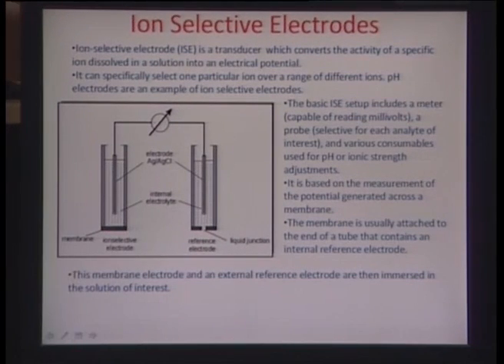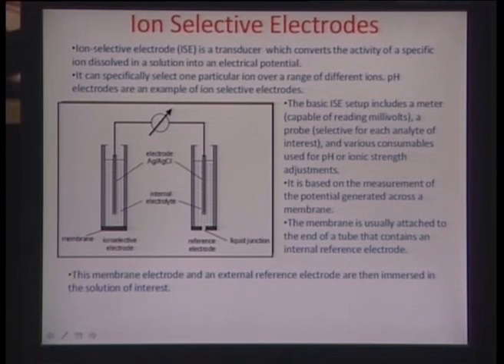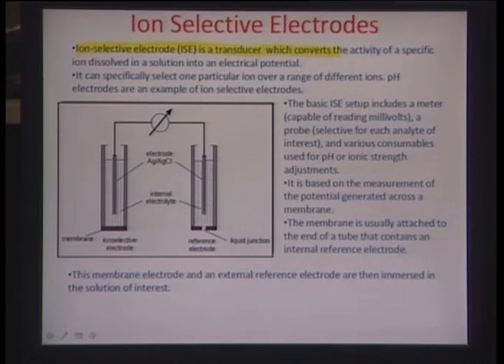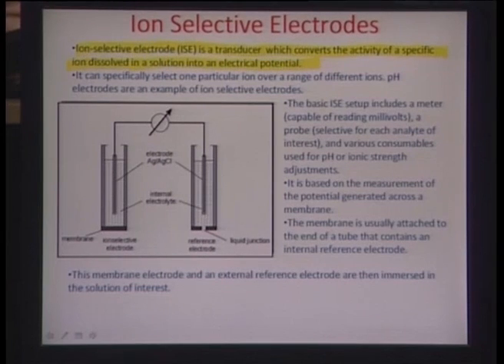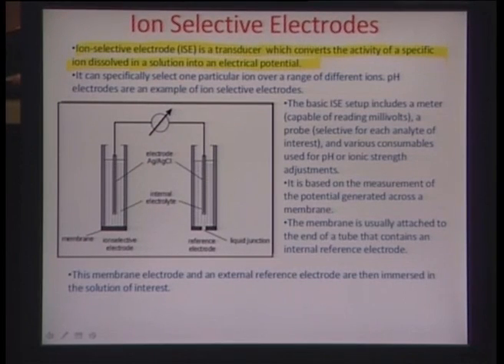We are very often faced with the problem of detection where there are more than one competing ions in a solution, and we want to find out a particular ion of interest. The ion selective electrode is a transducer which converts the activity of a specific ion dissolved in a solution into an electric potential — even though there are more than one ion type in solution, only the ion of interest is reported.